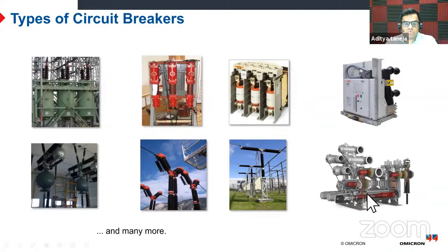We see this very commonly in Saudi Arabia and most of the GCC, and they are replacing the old types of breakers. They are still being replaced, and the new ones coming in are all GIS. So I will give some more focus to this while talking about my testing work. And this is not enough, as there is too much variety of high voltage breakers also, so I cannot give you a very simple overview there.